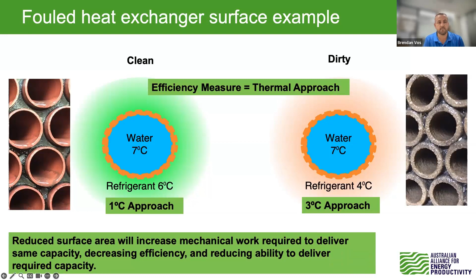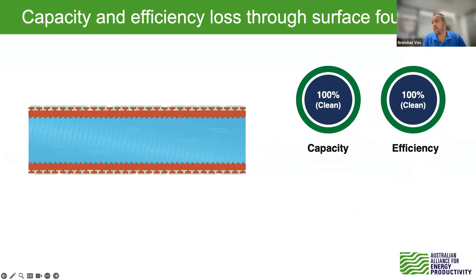Here's a nice clean tube that runs through a heat exchanger. Nice little grooves on the inside, which increase surface area. Typically 100% capacity, 100% efficiency when they're clean. But when I make a nice little bit of scale over the top of those, we can get, at an extreme, down to 70% of the capacity and drop to about 80% of the efficiency, as just a rule of thumb. So here we come along with our nice tube brush, which goes very well with that pipe cleaning we just looked at, except much less advanced. We become nice and clean and back we go, basically. So we've picked that 20% back up.